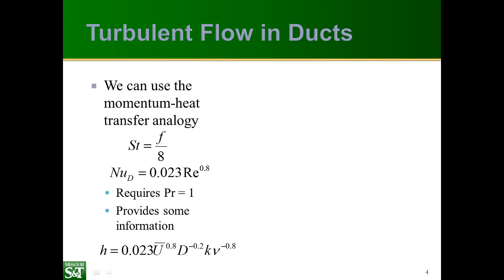This is useful, but it's also a problem because those small tubes with high velocities also have the largest pressure losses, which means you'll require large pump power. So there's an engineering optimization problem here between optimizing the heat transfer and optimizing the friction losses.